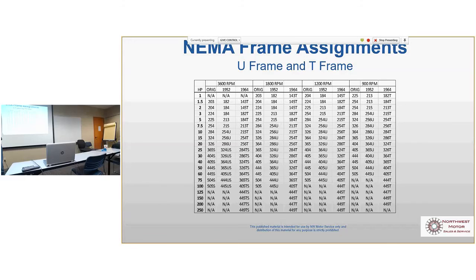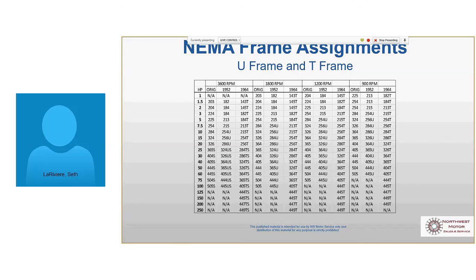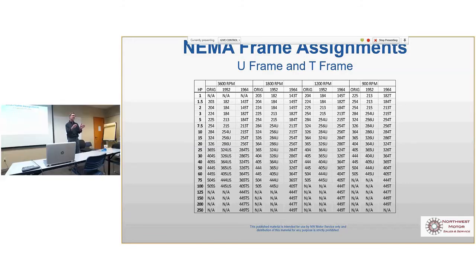The other thing that's not a standard dimension is the overall diameter of the motor. The shaft height and so on is standard, but the diameter of the frame could be longer or wider or smaller. Reliance particularly makes very skinny, long motors. So if you're replacing a Reliance in a tight spot, another motor might not fit, so you might see that occasionally. If you're replacing what should be just a standard frame for frame, it'll be great unless you've got unusually tight space limitations. Most people wouldn't put something up a wall 1/2 inch away from the motor, but it happens. So if it's really tight like that, then let us know. Otherwise, you probably are going to be okay. All the other dimensions are going to be standard. It's just the length and the diameter that can be off slightly.